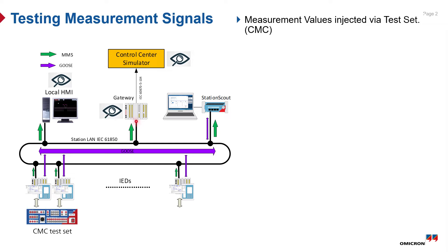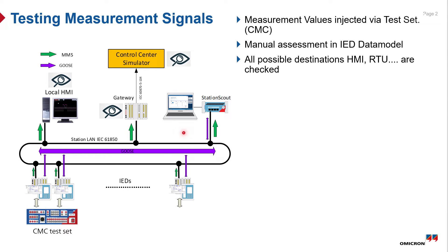We can also check different destinations these signals are communicated to, such as gateway, local HMI, or another test client like IED Scout. Please note that the values injected by the test set may differ slightly with the values read from the IED. For that, we have a 5% margin to make it easier to assess the result. Alright, let's proceed to test now.